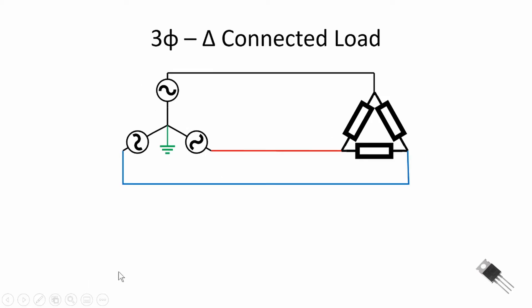We can also have delta-connected loads. In a delta-connected load we look from line to line — for example, A to B — which is called a line-to-line voltage. Go back and review your motors or machines class where you learned polyphase voltage. This is 208 volts RMS, and referencing our line-to-neutral phase angle, it's at a phase angle of 30 degrees relative to our A line-to-neutral. We can also have B-to-C and C-to-A line voltages across a delta-connected load.